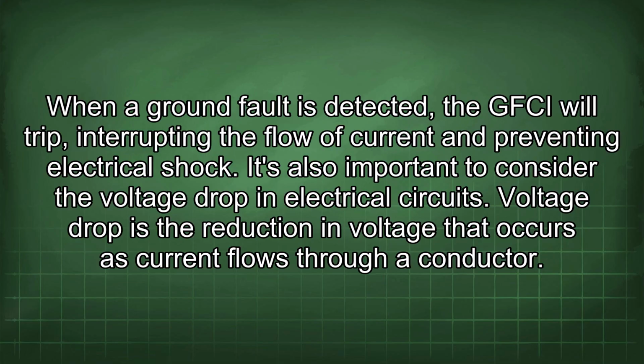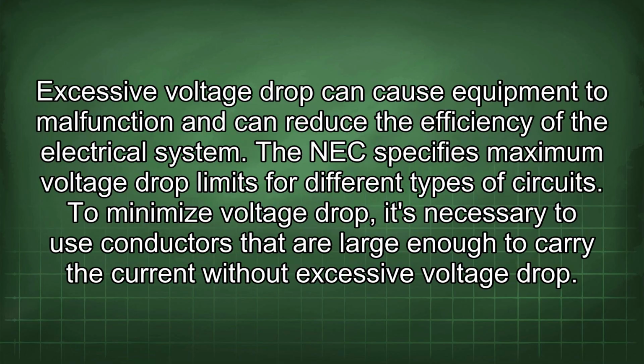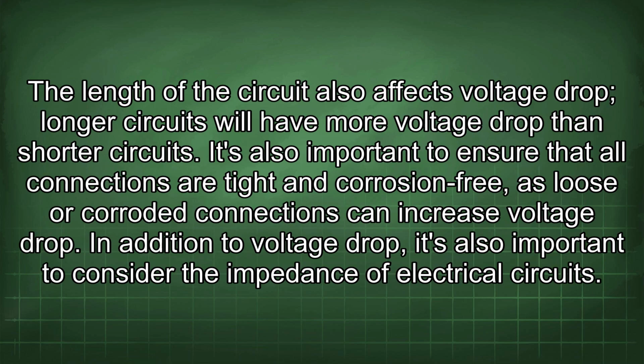It's also important to consider the voltage drop in electrical circuits. Voltage drop is the reduction in voltage that occurs as current flows through a conductor. Excessive voltage drop can cause equipment to malfunction and can reduce the efficiency of the electrical system. The NEC specifies maximum voltage drop limits for different types of circuits. To minimize voltage drop, it's necessary to use conductors that are large enough to carry the current without excessive voltage drop. The length of the circuit also affects voltage drop. Longer circuits will have more voltage drop than shorter circuits.